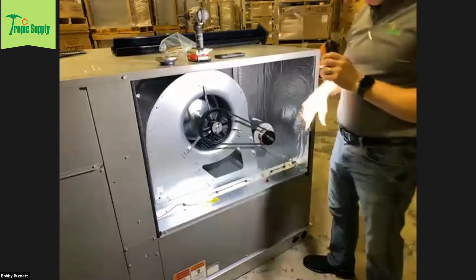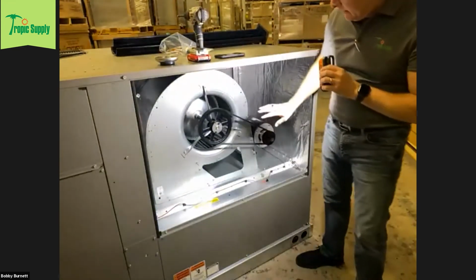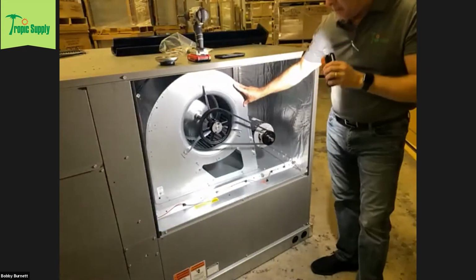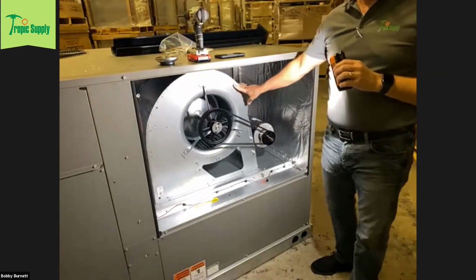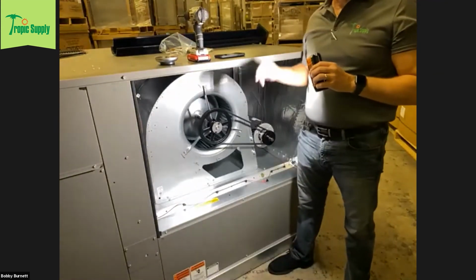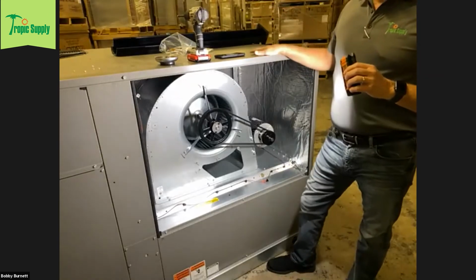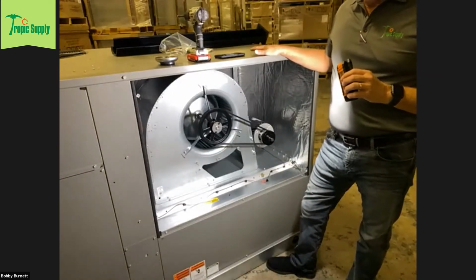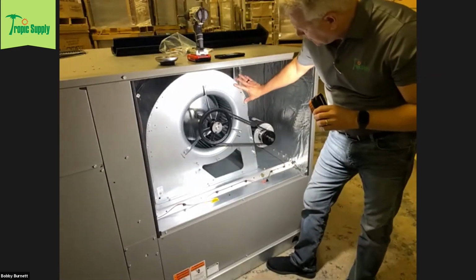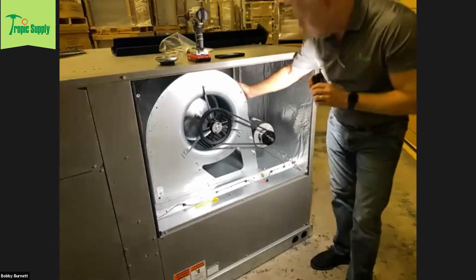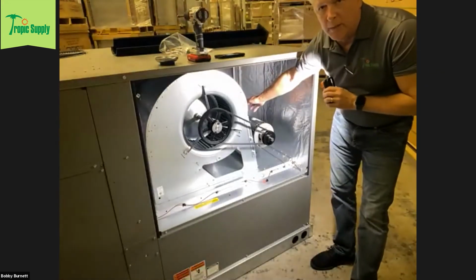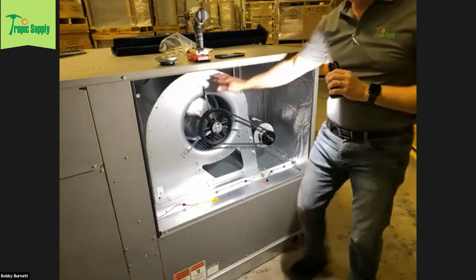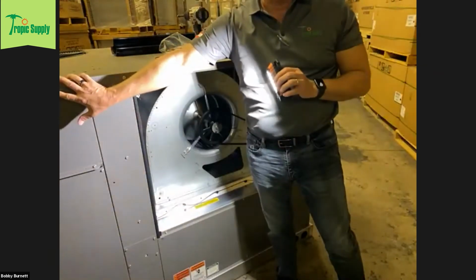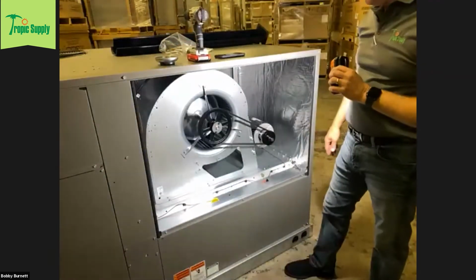Before I do that, let me back up a second. There are some mounting holes on the blower assembly for accessories. You can order these units with variable frequency drives. There's an actual bracket that mounts here for the variable frequency drive. You'd unplug the motor, plug it into the drive, and route your wires through here into the electrical panel to hook it up.